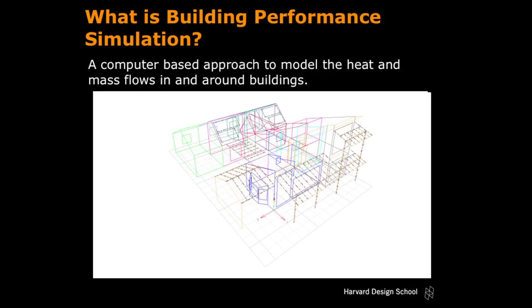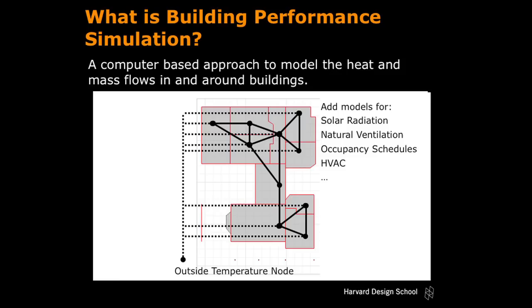When you want to model a building like this in the computer, you abstract the building. You say: I have a building that consists of different thermal zones, and each zone is represented as a node. You then have this nodal network that's automatically set up by a computer that defines the relationship between the rooms and the outside. You add components for occupant behavior, solar radiation, and so forth — and there you have your thermal simulation program.